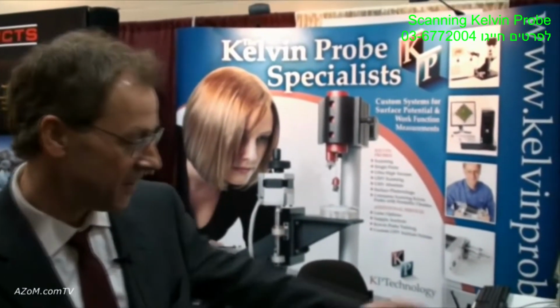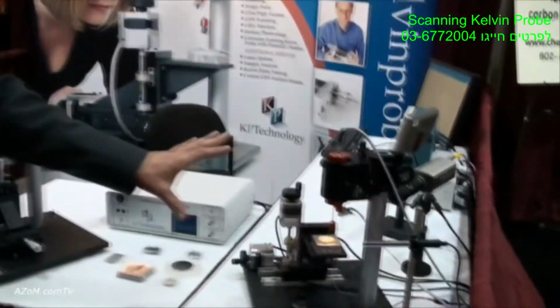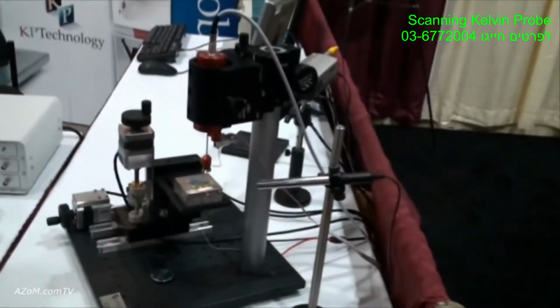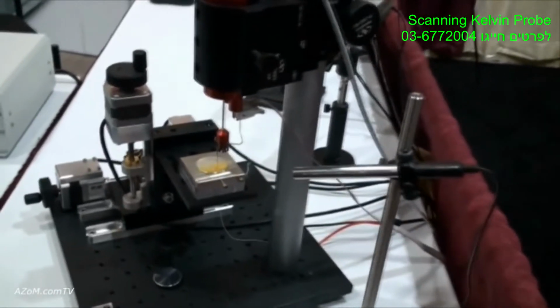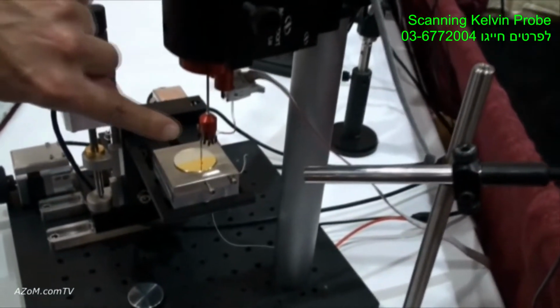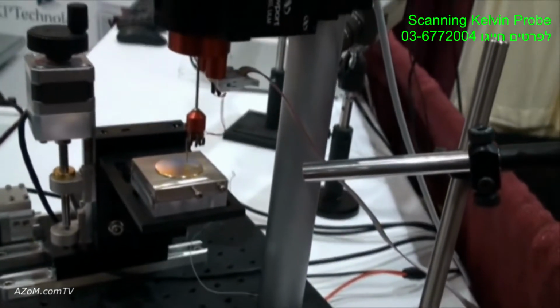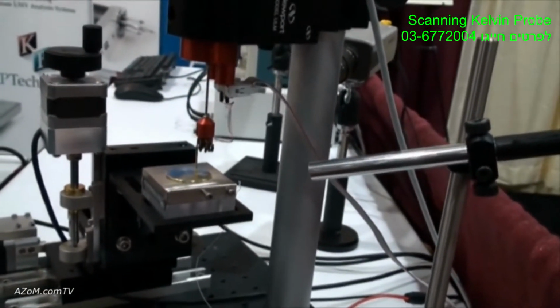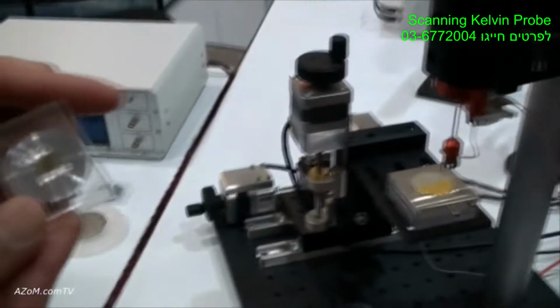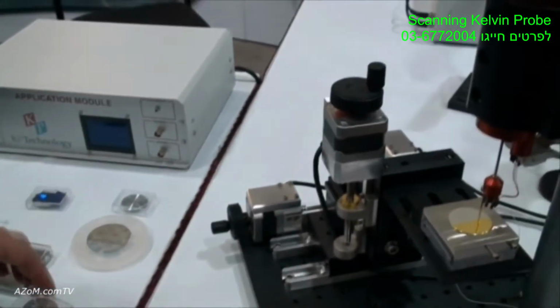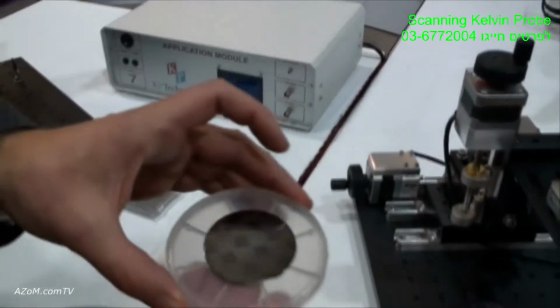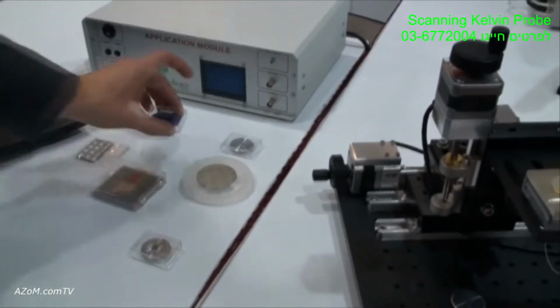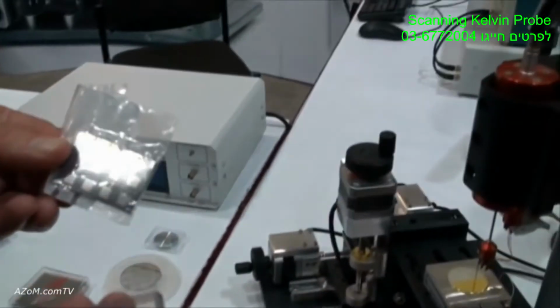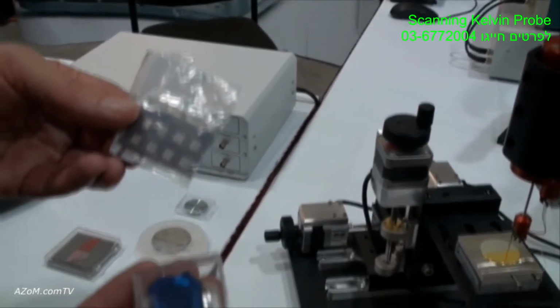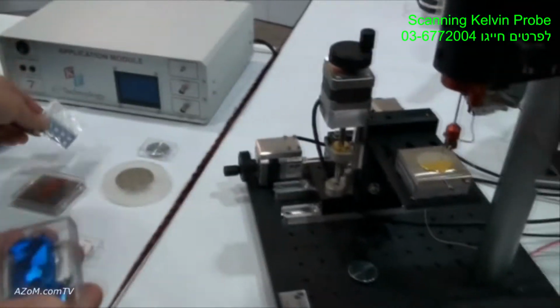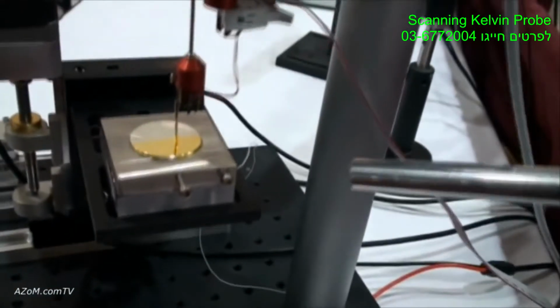Thank you. Here, this is a scanning Kelvin probe system. The sample is aluminium and gold, and the Kelvin probe measures the work function difference between a vibrating tip here and the material under the tip. The material under the tip could be a metal, as in this case. It could be a device, as in this case, which is a single electron transistor device. It could be a wafer with a pattern on it, and it could be different types of solar cells. And this technique is used for corrosion studies, for polymer films, for polymer electronics, and for material studies.